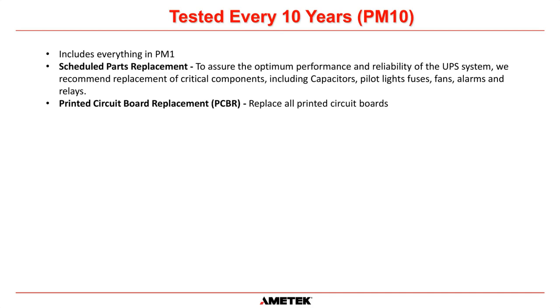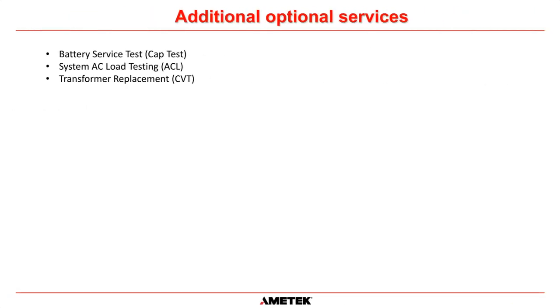So that's why it's critical to follow the maintenance procedure. And additional optional services that you can get when you're doing your PMs is we can do a capacity test on your battery. You can do a full system AC test. We can put a load bank on the output of your UPS and run it to full 100% load and make sure that it is still able to do that. And we also offer, for very old constant voltage transformer systems, to replace transformers that are showing signs of failure or that have actually failed.